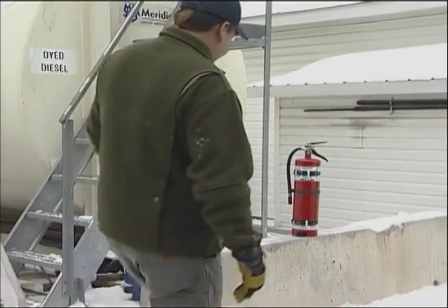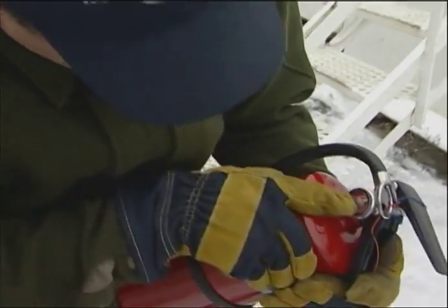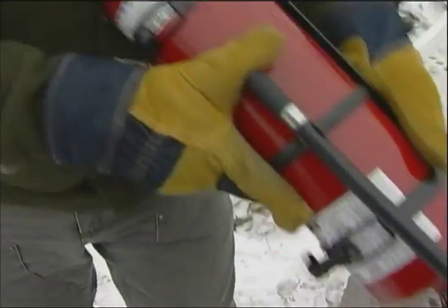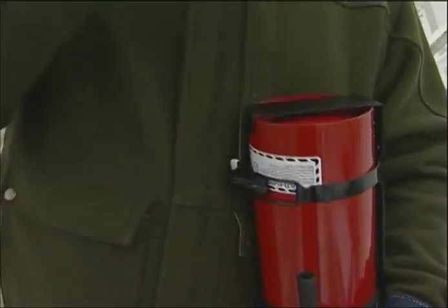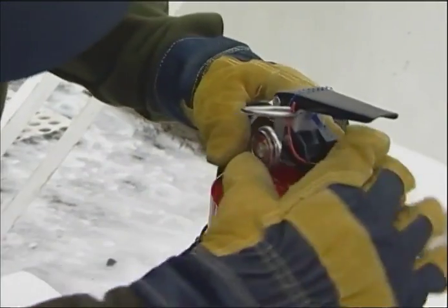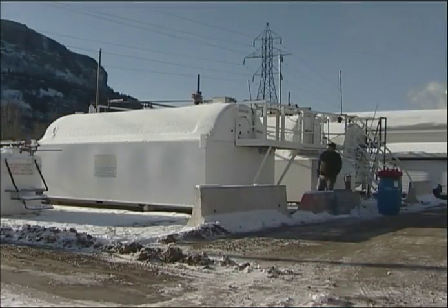A minimum of 1 20-pound fire extinguisher or 2 10-pound fire extinguishers in proper working order must be on site. Extinguishers must be inspected on a monthly basis and signed off by an operator. Extinguishers must be stored in a highly visible location and stored in a manner in which they cannot be tampered with.